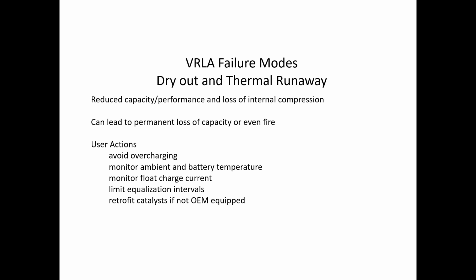It did happen within a year period, but somebody under quarterly or even semi-annual maintenance would have picked up on that issue before. At that point someone had noticed it smells like sulfur or rotten eggs, a pungent smell, and then physical heat off the battery. By the time you get to that point, it's beyond repair. So avoid overcharging, and monitor ambient temperature and battery temperature. Usually we look for a difference between those two. Also monitor float current, and limit equalization intervals if you do have to equalize at all.